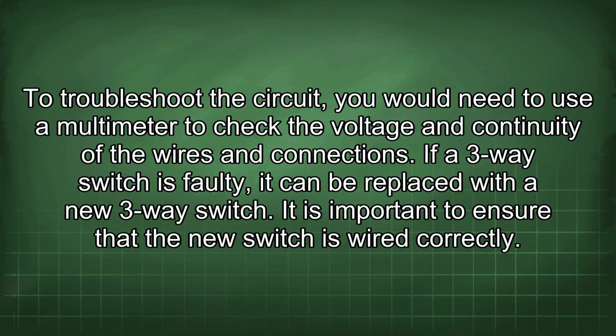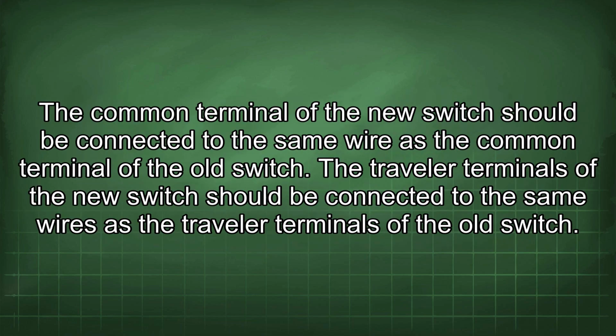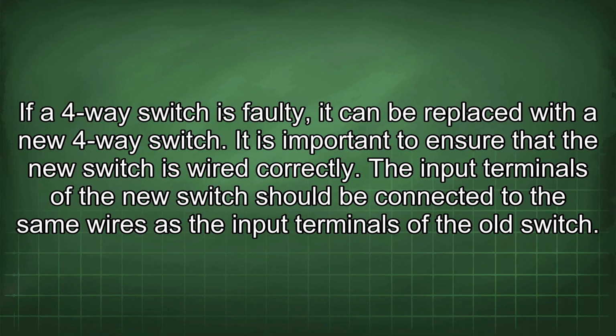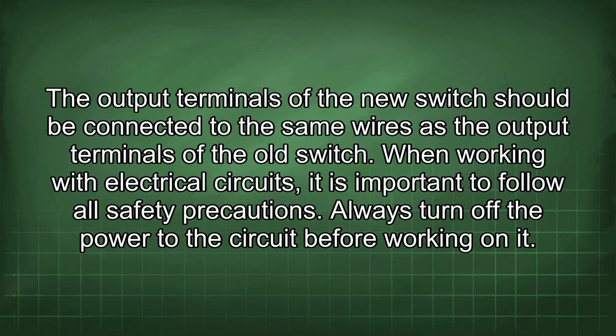It is important to ensure that the new switch is wired correctly. The common terminal of the new switch should be connected to the same wire as the common terminal of the old switch. The traveler terminals of the new switch should be connected to the same wires as the traveler terminals of the old switch. If a 4-way switch is faulty, it can be replaced with a new 4-way switch. It is important to ensure that the new switch is wired correctly. The input terminals of the new switch should be connected to the same wires as the input terminals of the old switch. The output terminals of the new switch should be connected to the same wires as the output terminals of the old switch.